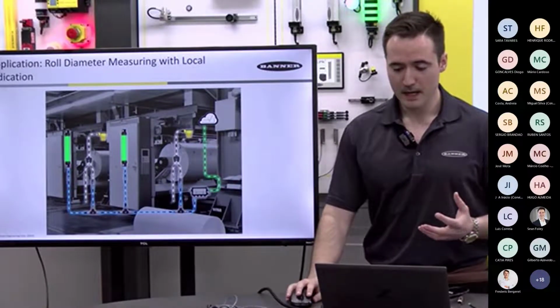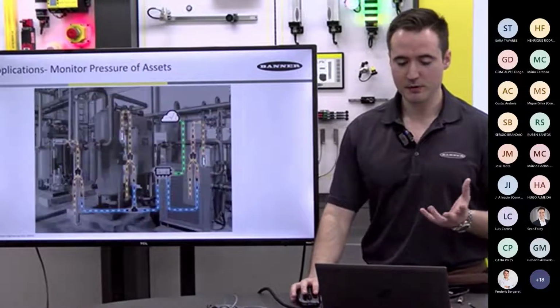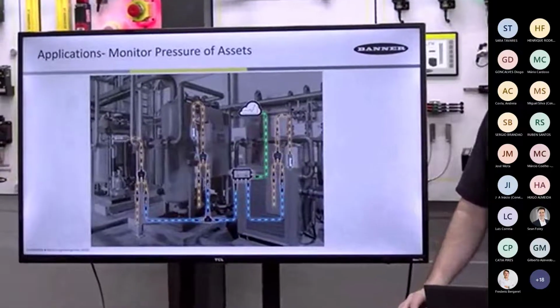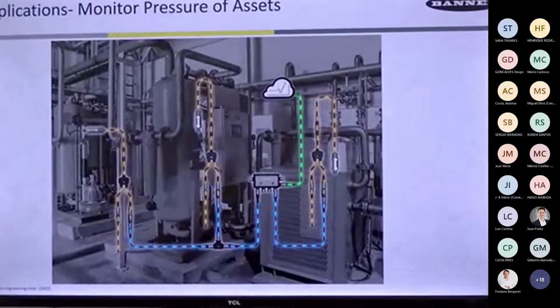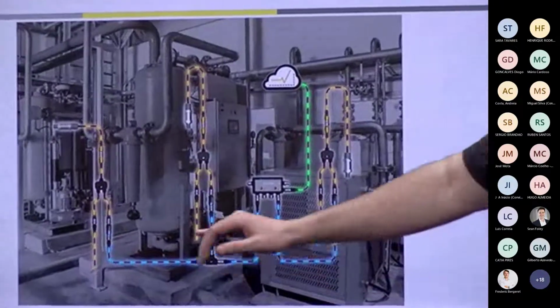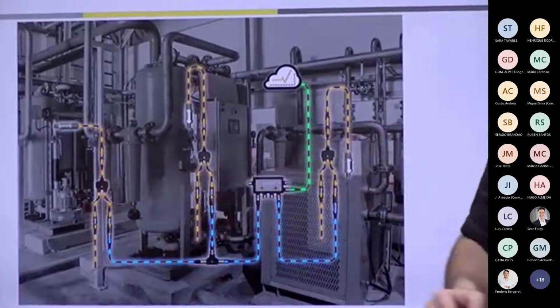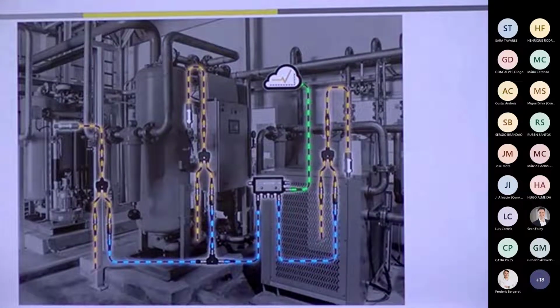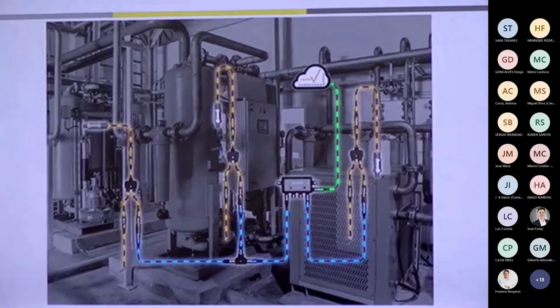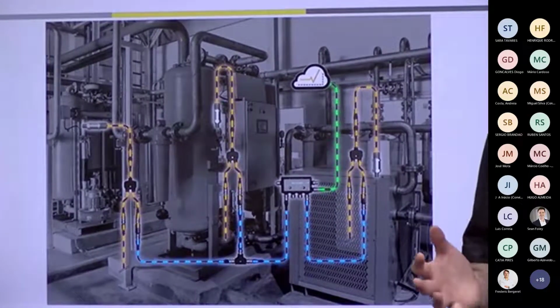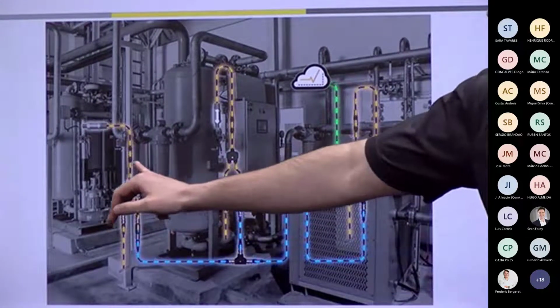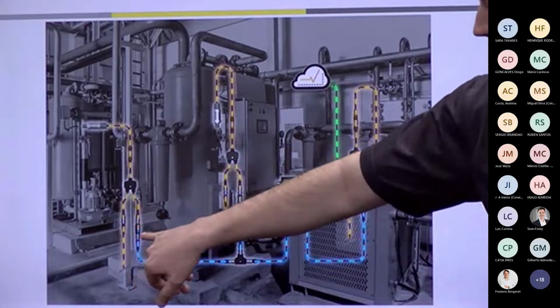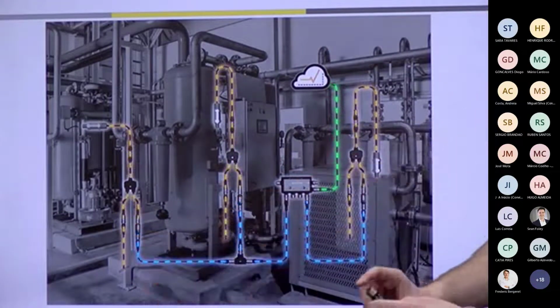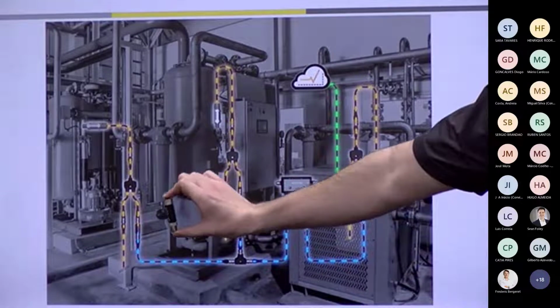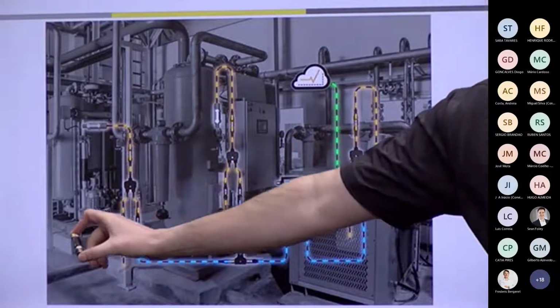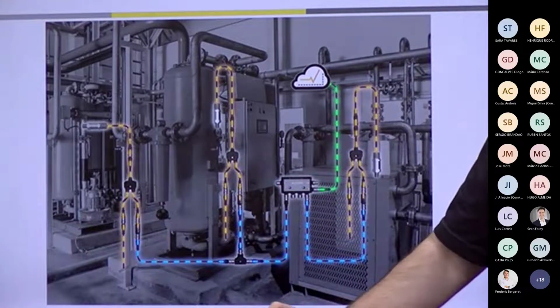Let's talk a little bit about some other applications, maybe pressure. You want to continuously monitor pressure in certain applications. A lot of pressure sensors have a 4 to 20 milliamp output, and there are many different manufacturers of pressure sensors with a 0 to 10 volt or 4 to 20 milliamp output. We could convert that signal over. As you can see, there's the compact converter right here, about the size of a AA battery. If you want to send that sensor signal back to your PLC, you could do that.